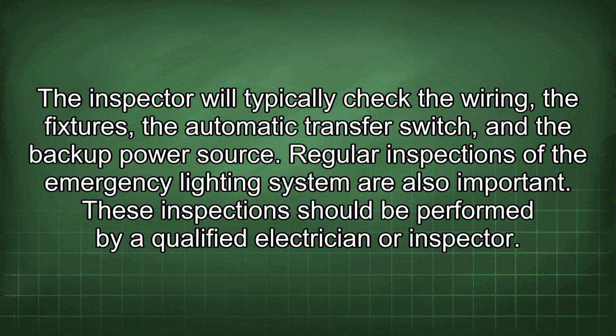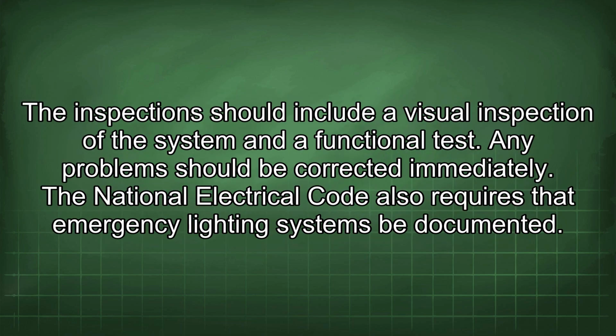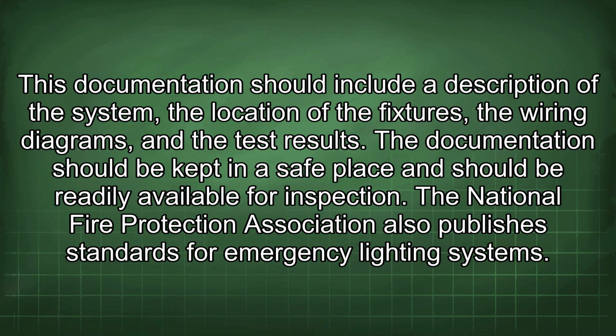Regular inspections of the emergency lighting system are also important. These inspections should be performed by a qualified electrician or inspector. The inspection should include a visual inspection of the system and a functional test. Any problems should be corrected immediately. The National Electrical Code also requires that emergency lighting systems be documented. This documentation should include a description of the system, the location of the fixtures, the wiring diagrams, and the test results. The documentation should be kept in a safe place and should be readily available for inspection. The National Fire Protection Association also publishes standards for emergency lighting systems.